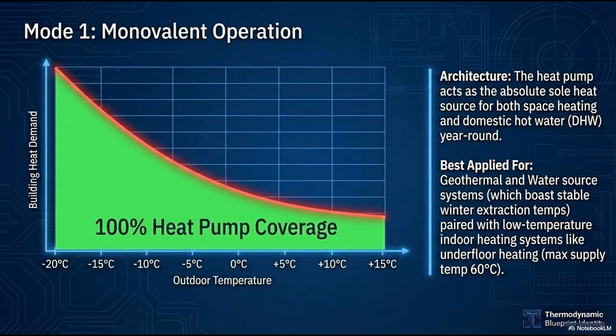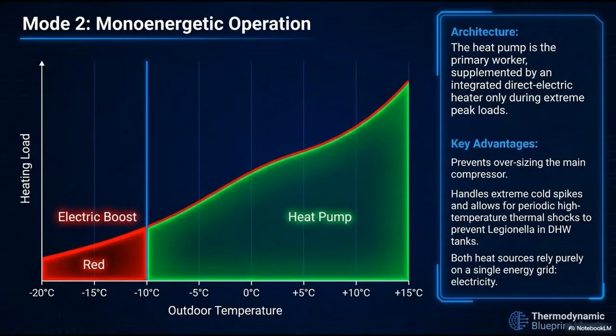Because that sounds like an absolute nightmare. The guide addresses this exact fear, and the solution is deeply reliant on modern insulation. It is true that traditional radiators were designed for 90-degree water, but we have to ask why they needed to be that hot. Historically, they were over-engineered to compensate for incredibly drafty, poorly insulated buildings.